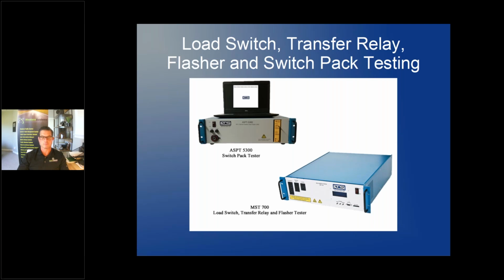So unfortunately, where you used to be able to just use the PCMT 8000 to do your conflict monitor testing, in the ATC cabinet you really need two devices: you need to test the CMU and you need to test the switch pack. If you don't, it's pretty much equivalent to running a test on a NEMA TS2 monitor and skipping all of the channel voltages, which would be highly dangerous to do.